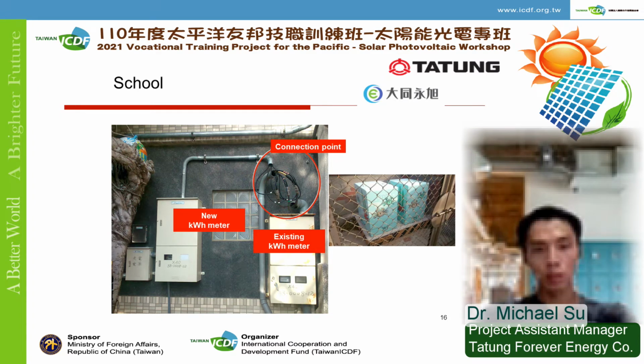The previous case is on the pole. Now we look at the case of the demarcation point set underground. You can see that there is an existing old meter on the right hand side, and there is a cable down the box connecting into the ground, which leads all the way to the transformer's side. In such a site, sometimes we create a new connection point on top of the existing meter, which connects to our new meter set by the side. In this case, the demarcation point is at the connection point between the old and the new meter.